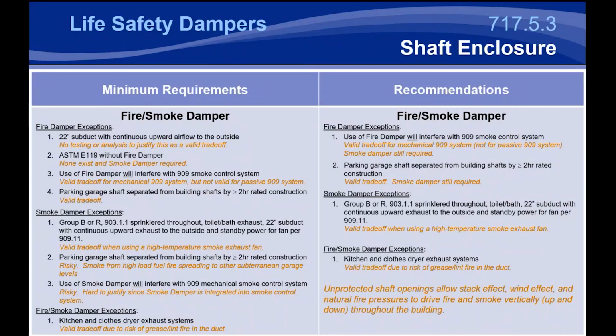Now, when you're dealing with these exhaust shafts, there is a requirement for the fire damper that you can remove and the smoke damper. And you can certainly do that, but the requirements are a bit different.